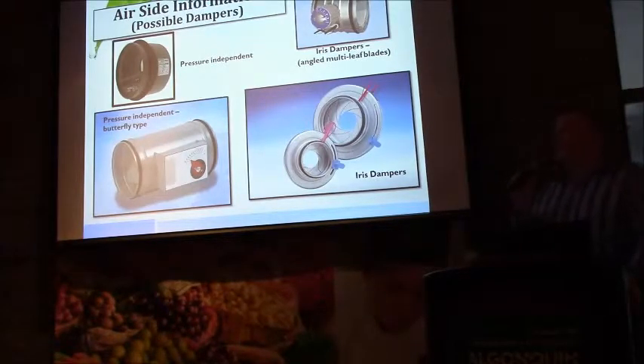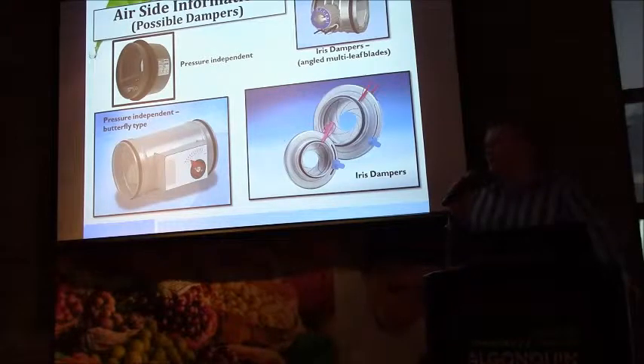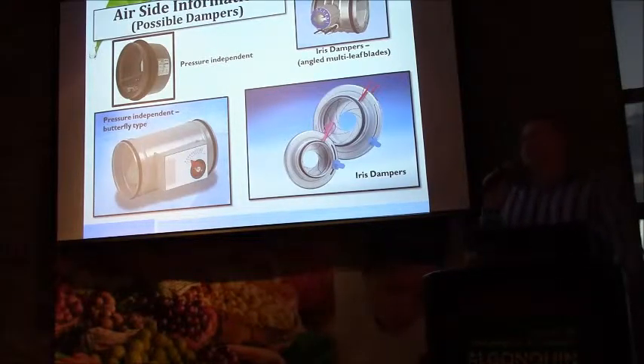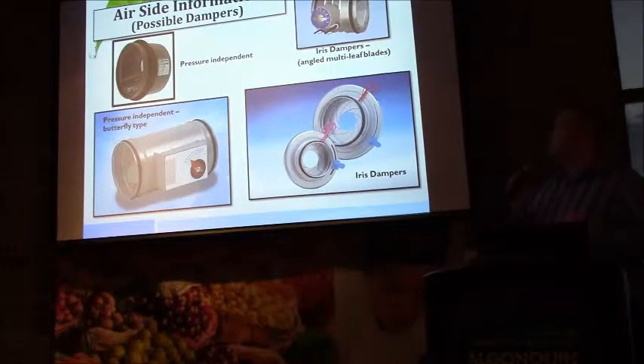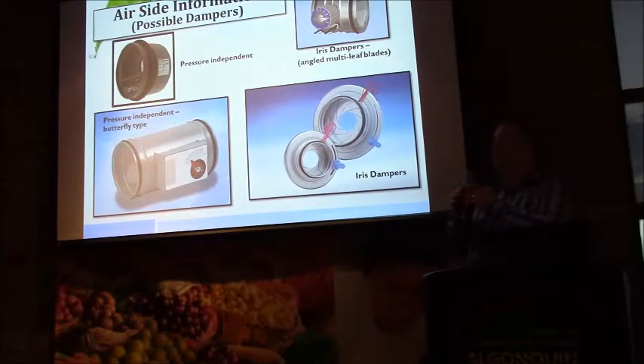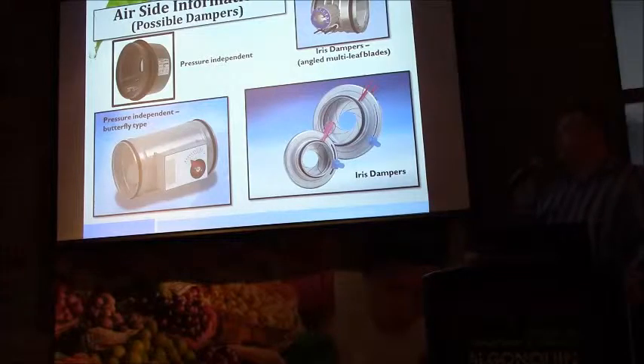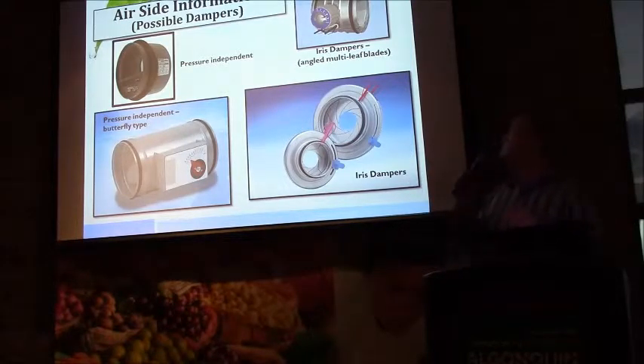Pitot traverses, as a general rule, for active beam systems don't work because the duct velocity is too low to support the proper measurement technique of integrating that profile in order to determine the mass flow into the space. So these are generally preferred. They're a little more expensive, but they're much easier to establish a branch flow than, say, a butterfly valve, which has two surfaces where they can trip the flow and create noise, and they're very sensitive to their positioning in order to set the downstream static pressure.